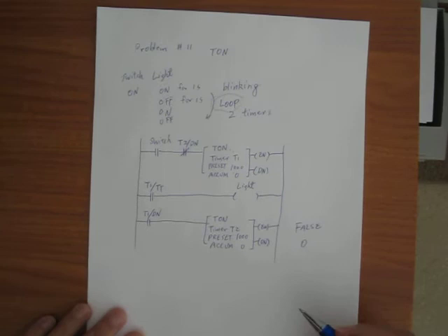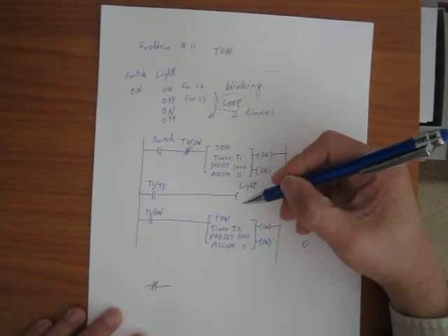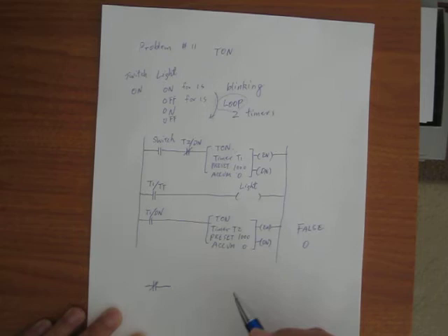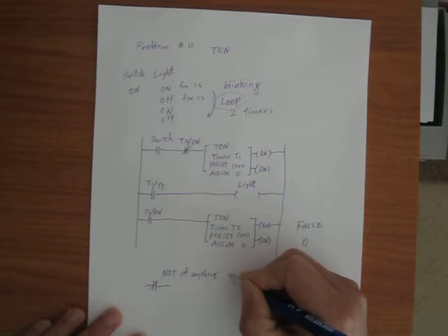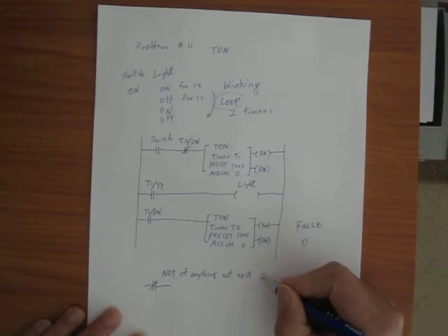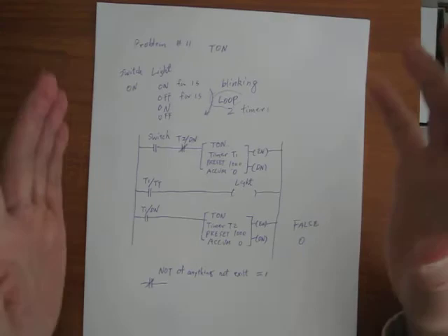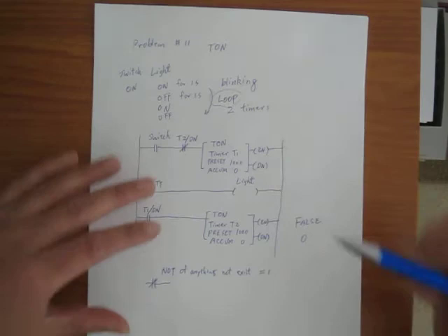This NOT gate — if you know how to use it, it's very powerful. All of that happens in a millisecond: turning T1 off and back on again. But you've got to be careful, because NOT of anything that doesn't even exist will be true — will equal 1. So if you made a mistake or referenced something that doesn't exist in the program, this will always be true. You've got to be careful, but this is a valid method to loop it.